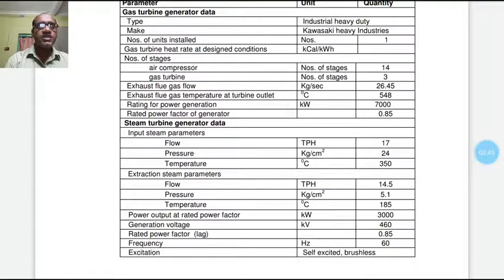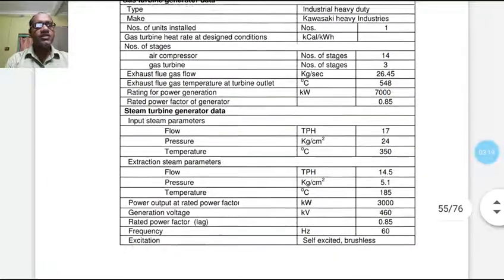Steam turbine generator data: flow 17 TPH, pressure 24 bar, temperature 350 degree centigrade. Extraction steam parameters: flow 14.5 TPH, pressure 5.1, temperature 185. Power output 3000 kilowatt, generation voltage 460, rated power factor 0.85, frequency 60. Excitation is self-excited brushless.